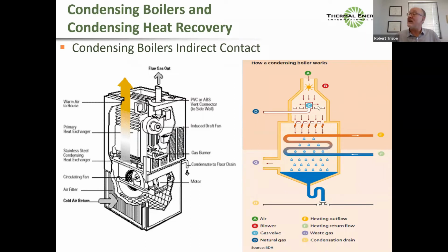Basically it's quite simple. I like this schematic on the right, although it's kind of a hacked schematic. The basic thing it's showing is you've got combustion air, you've got a flame, but the flame is on the outside of the tubes. Your water's coming in, cold water coming in the tubes, getting heated by the flames, just like in a boiler, except we're not boiling. And the cold water comes in and goes out hot. The condensation happens on the outside of the tube.